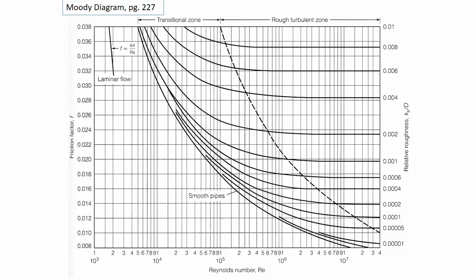You assume a flow rate, calculate an F value, see if that F value matches up with the flow rate that you assumed, and you converge on a solution, and it'll eventually work out. That's an accepted technique. But what makes it a little bit tricky is if every time you calculate, you have to go back to a paper figure and run your fingers along the lines and look for the point of intersection, that can be the weak link that takes a lot of extra time.